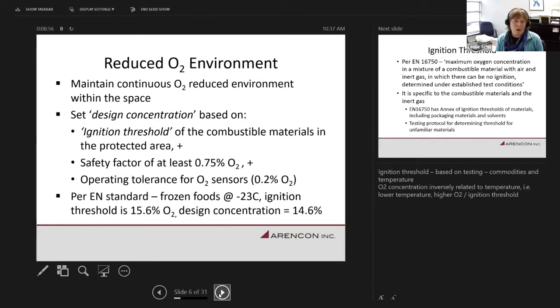So what we're talking about as far as this reduced oxygen environment, and how we get to the correct level, the continuous oxygen reduced environment within the space. What has to be established for the system to work is essentially a design concentration. We have to say, this is the concentration of oxygen that we want to hold in this space. It will fluctuate slightly. That's going to happen as we have losses in the space with doors being open and the natural tendency for the space to want to revert to ambient. So we will see some fluctuation in the oxygen concentration, but it's going to bounce in a bandwidth of a high and a low.